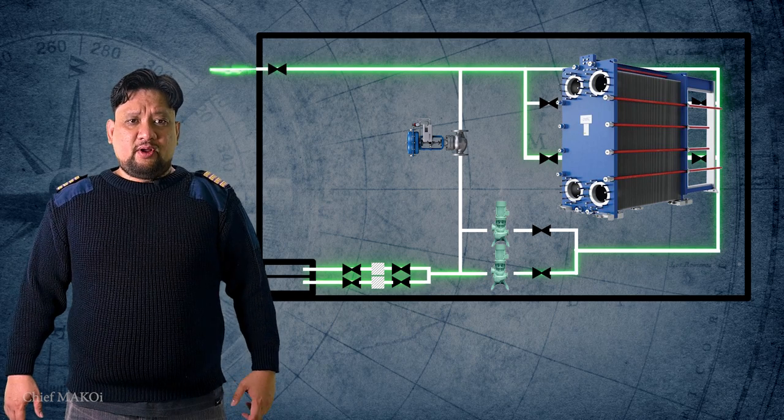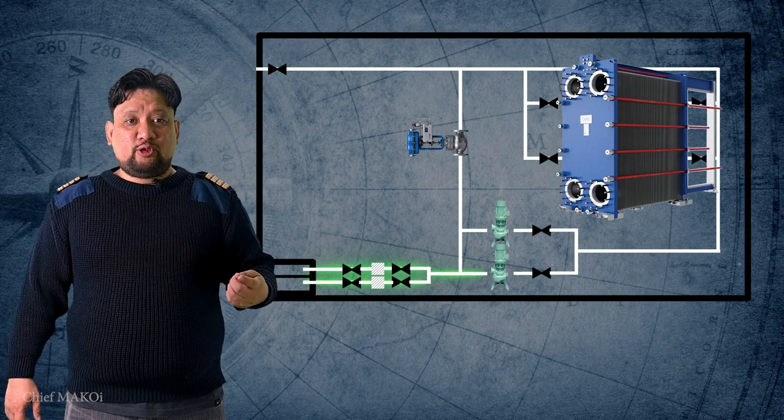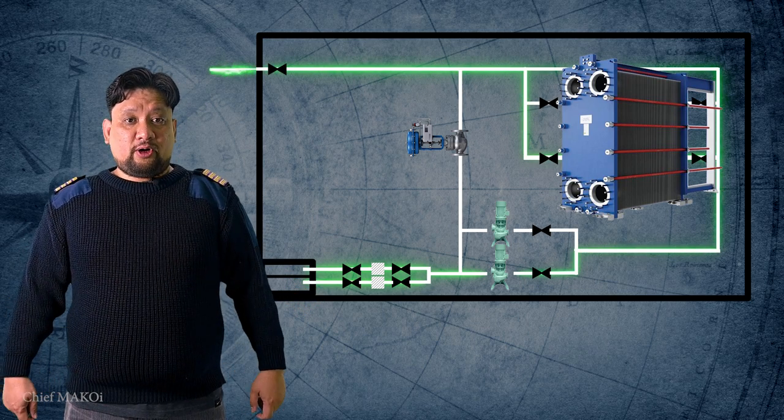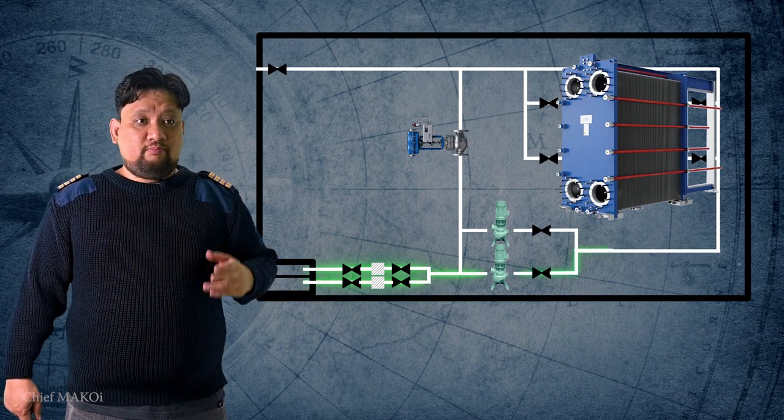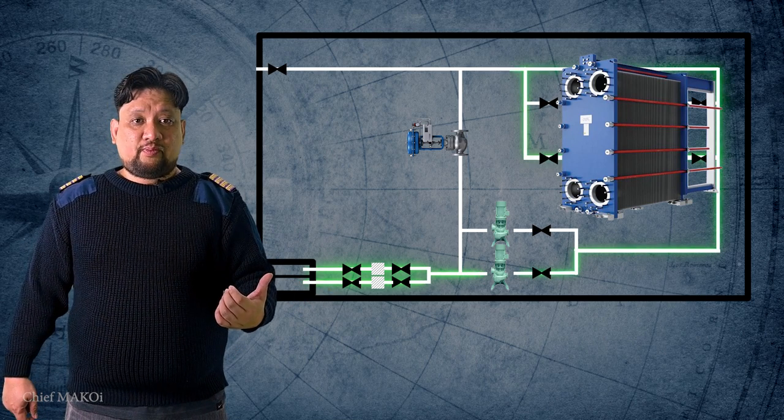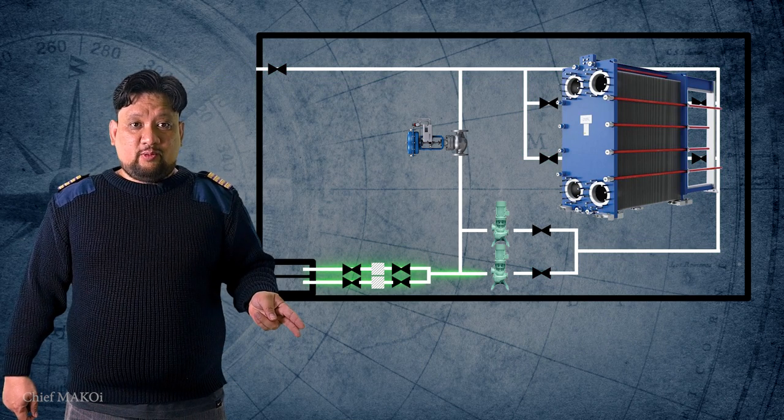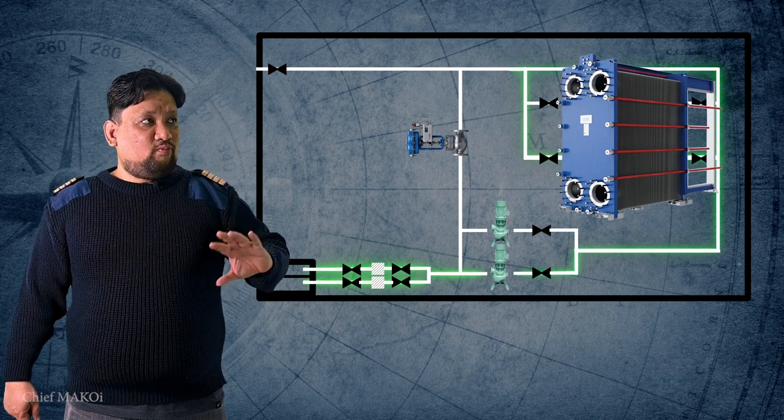In this type of system, fresh water running in a closed circuit is the medium that goes through all the other heat exchangers. And this fresh water, after absorbing all the heat from the various systems, passes through the central cooler where it will transfer all of the heat to the seawater, which then exits the system and goes back out to the sea.